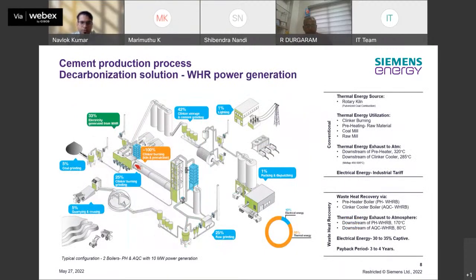The decarbonization of cement production process starts with waste heat recovery power generation, where we have a preheater boiler, a clinker cooler or air quenched cooler boiler. And these boilers together can roughly generate around 33% of plant's total electricity requirement. However, this is not the end to decarbonizing cement production process. Different technologies exist today to further reduce the carbon footprint, such as by fuel shift to clean fuel like hydrogen, or carbon neutral fuel like biomass, carbon capture technology, etc. It's not uncommon today where the cement manufacturers are blending the total thermal energy requirement by biomass. The extent, however, is still restricted to 20% only.